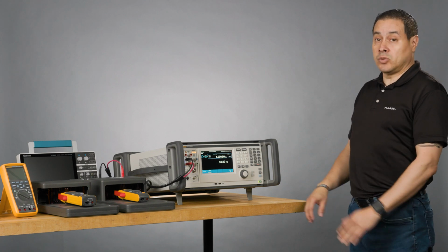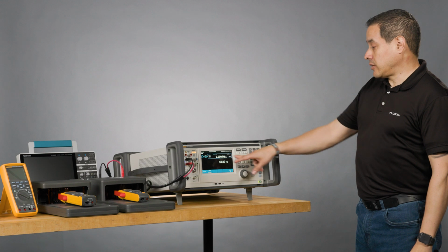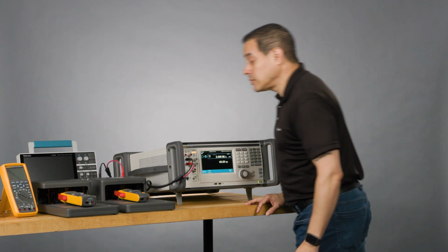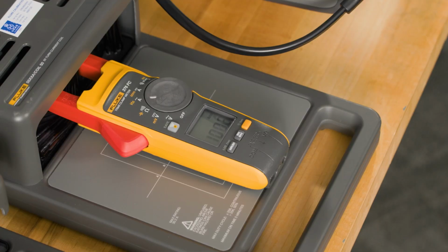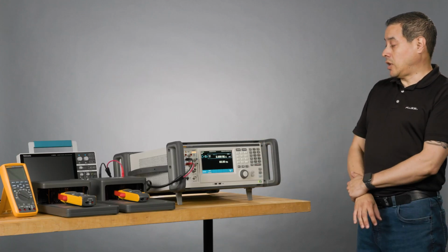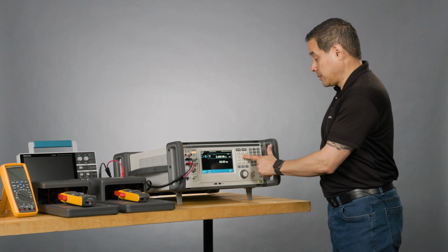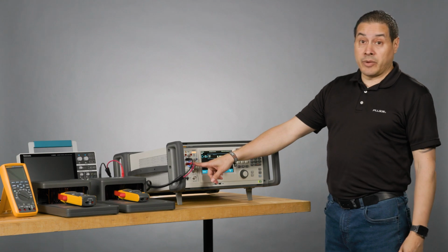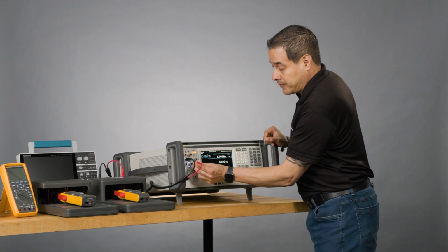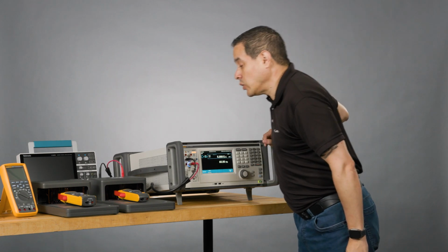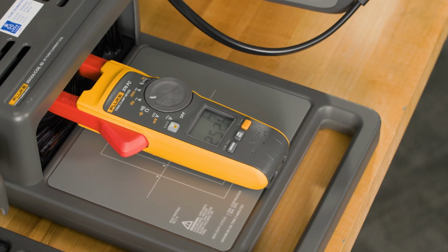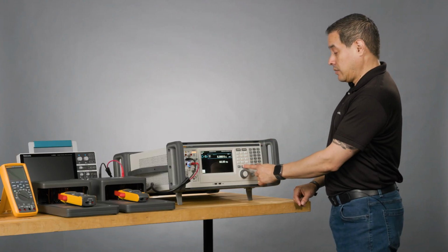I'm going to use the next point, which is 2 amps. 60 hertz, so I'm not going to change that. Same post. Looks good. Operate. And I'm reading 101.0. All is good. Stop. The next point is 5 amps. In this case, I need to stop because the calibrator is changing the post, so I need to be paying attention to that. No changes there. All is good. So 5 amps, I'm reading 252.8. And standby.